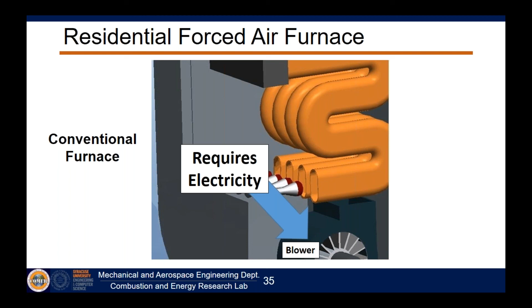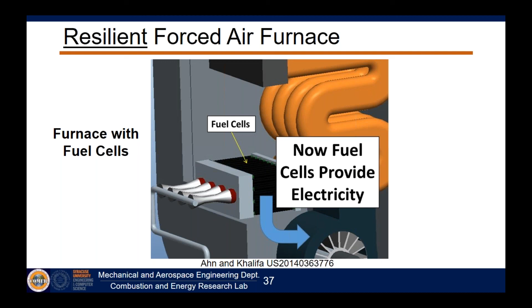Now, if we change it up a little, we put a fuel cell stack between the burner and the heat exchanger, essentially making a two-stage combustion with fuel cell power. Now we can provide that power directly to the blower, so this furnace not only provides heat but also its own electricity. Why is that different than a typical fuel cell? A typical fuel cell is fairly complicated, but we're not steam reforming, so we don't need all these heat exchangers — our system becomes significantly simpler. We just allow the combustion process to handle all the reforming and thermal management of the fuel cell — much simpler.